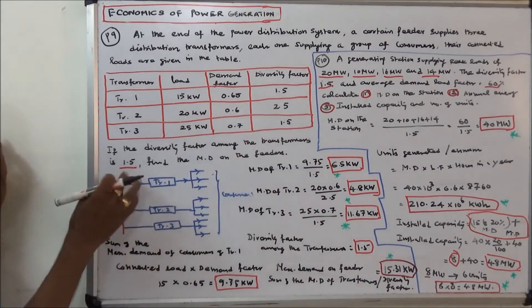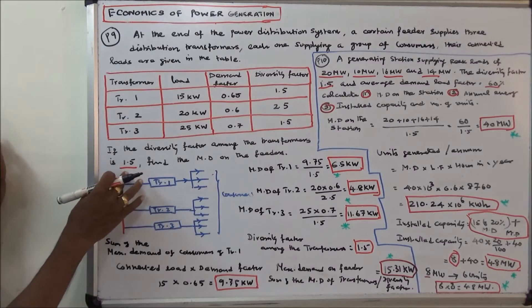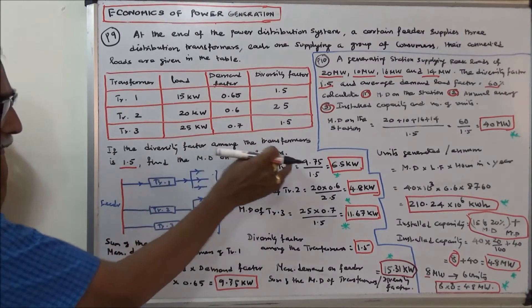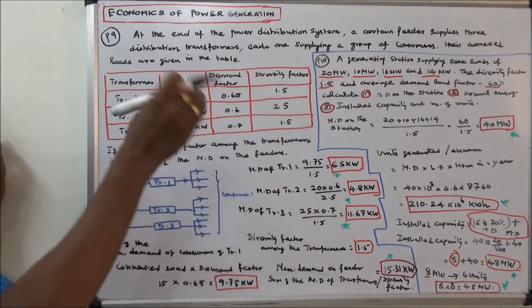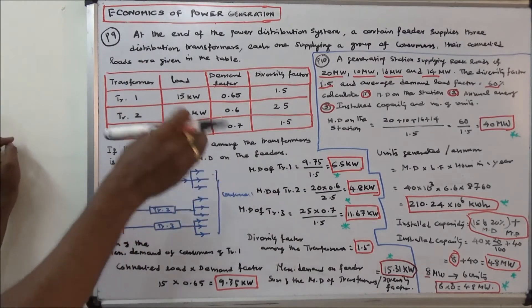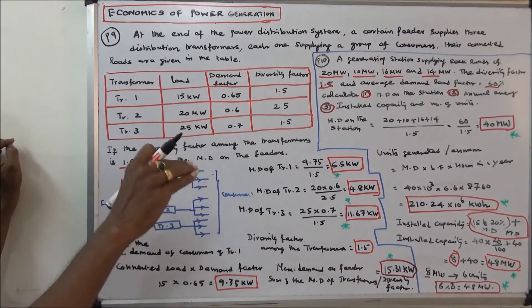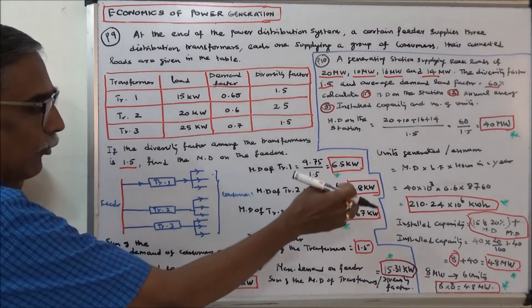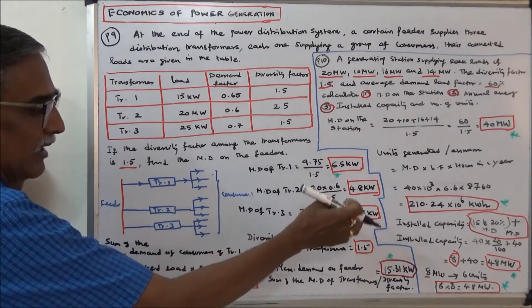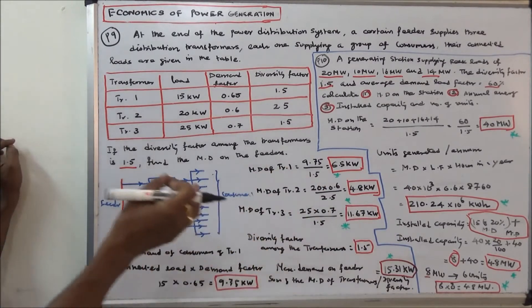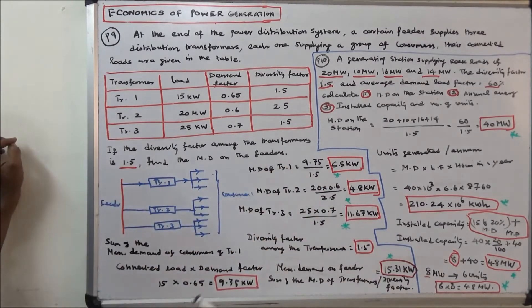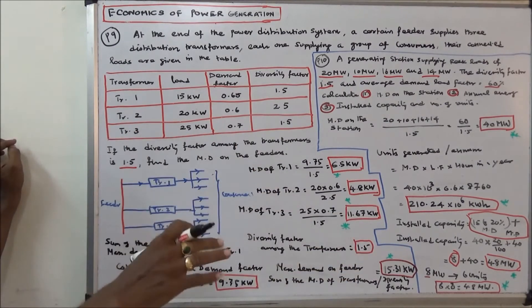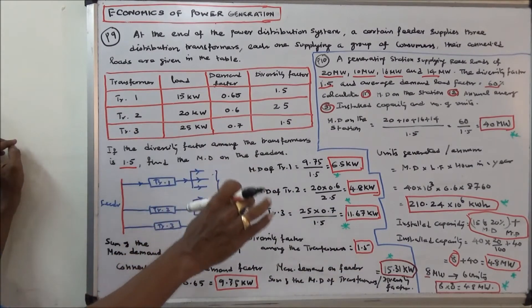The diversity factor among the transformers is given as 1.5. Therefore, the maximum demand on the feeder equals the sum of the maximum demands of the transformers divided by the diversity factor: 6.5 plus 4.8 plus 11.67, divided by 1.5, equals 15.31 kilowatts. That is the maximum demand on the feeder.